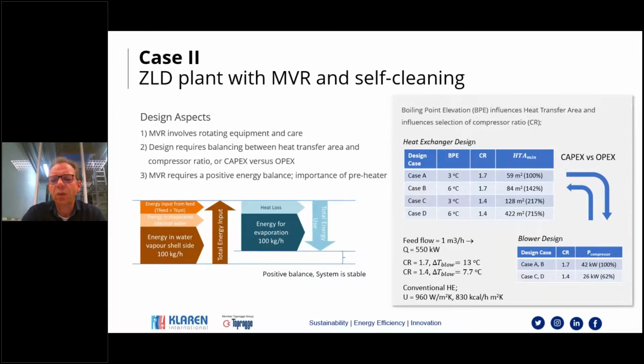But this has one aspect that I also should refer to, and that's boiling point elevation. Boiling point elevation you will have with effluents, since the composition of the effluent with salts and its concentration will make the boiling point increase, meaning that if I have water with a salt, it will at atmospheric conditions not boil at 100 degrees, but maybe at 103 degrees. But still, if I evaporate at 100 degrees, it will still condense, because then it's water again at 100 degrees. So this boiling point elevation I lose when I look at my heat exchanger design.